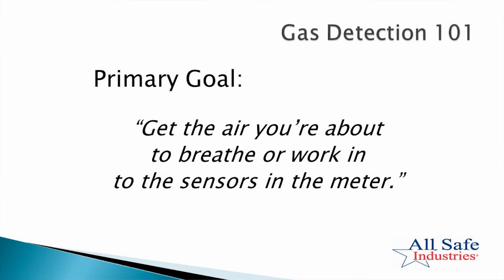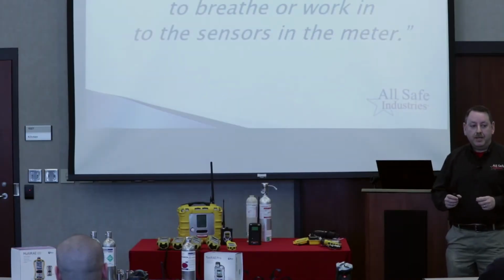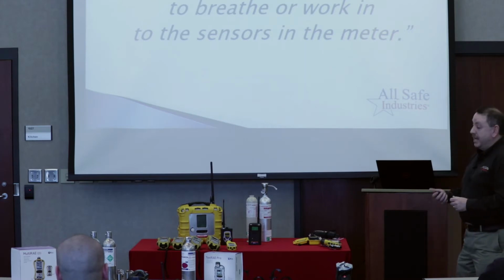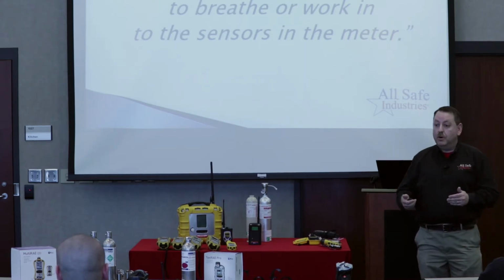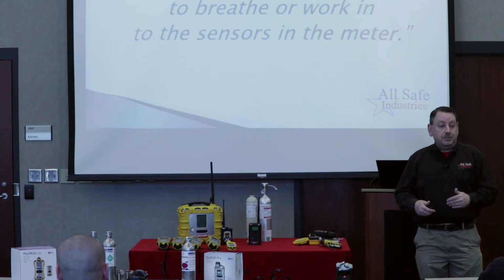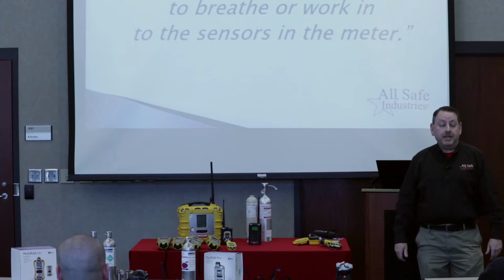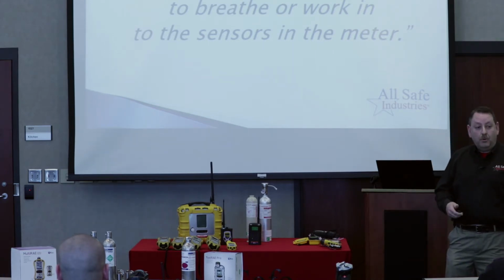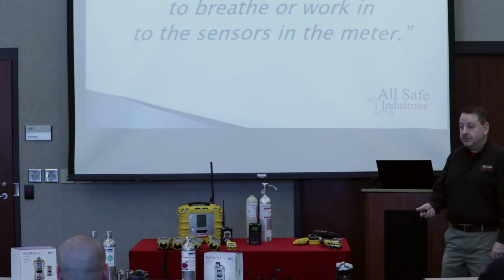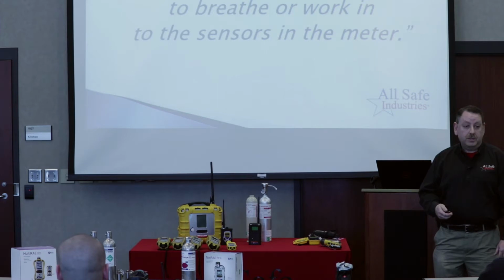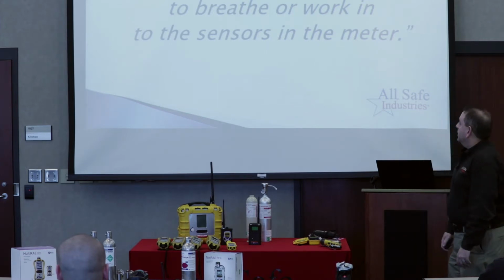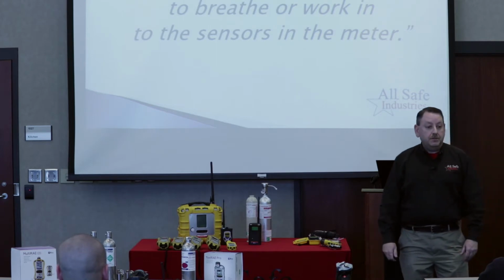Okay? All right. So the number one thing with gas detection, your primary goal, is to get the air that you're about to breathe or work in to the sensors in the instrument. There's a lot of little things going on in that statement. It's the air that you're about to breathe or work in, because we don't want a toxic gas that's going to be dangerous to your health. We certainly don't want a flammable gas that could make something explode when you're in the space, to the sensors in the instrument. That speaks to making sure you have the right accessories and making sure that the pump module and the unit are working properly. So just come back to this statement: get the air you're about to breathe or work in to the sensors in the meter. If you keep that as your baseline, you'll be good to go.